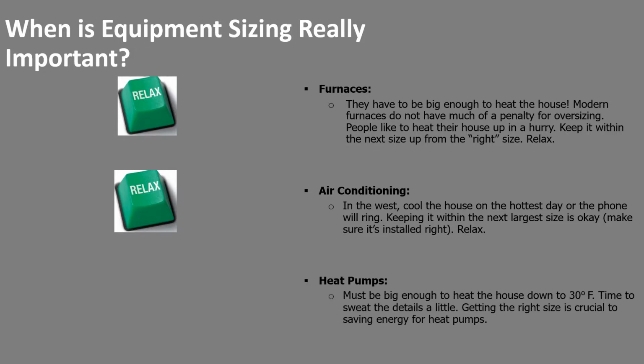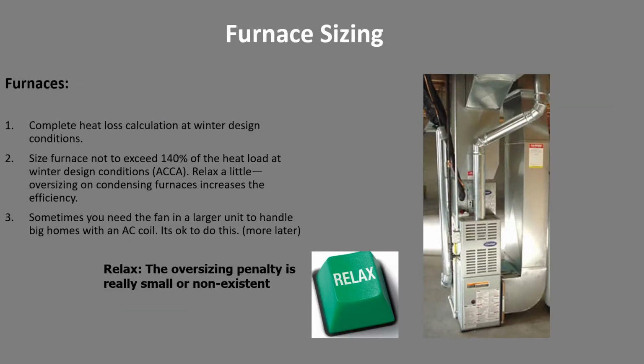Heat pumps. Heat pumps are a little more tricky to size. They have to be big enough to heat the house down to 30. That's our recommended balance point. It's time to sweat the details a little bit. Getting the right size is crucial to saving energy and making the occupants comfortable. It's probably not panic time, but the level of detail needed to size heat pump equipment is a little higher.